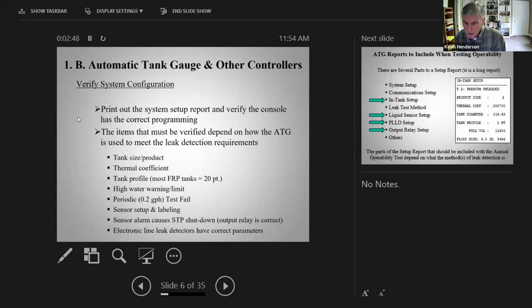And again, depending on what your method of leak detection is, you could have sensors connected to that tank gauge. You obviously need to make sure that the sensors are labeled correctly in the tank gauging system. You might be required to have STP shutdown if the sensor goes to alarm. You could have a PLLD that's required to be programmed to shut down STP. So it just depends on what your leak detection method is as to what parameters you need to verify are actually in the system correctly.